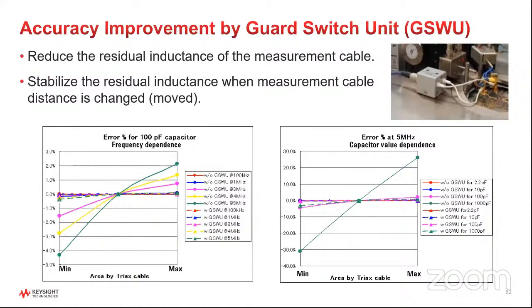So the benefit of having the guard switch unit is that by shorting those guards together when you're making a capacitance measurement, it stabilizes the residual inductance, especially if the cable gets moved around. So it will give you better results. Shown here on this slide is some data that, especially as you go to larger values of capacitance and higher frequencies, if you don't use the guard switch unit, you will get additional error in your measurement. In some cases, it can get kind of extreme, but again, it's a nice accessory. We normally recommend people use it. It doesn't cost very much, but it's a good accessory to have and use if you want to get the most accurate possible capacitance measurements when you're making a CV measurement.